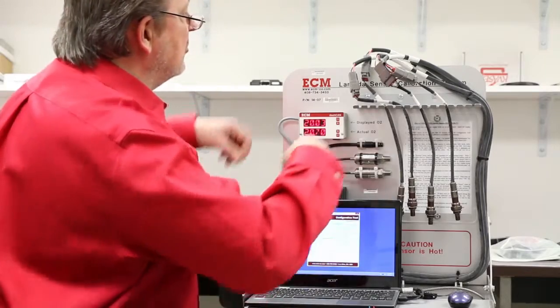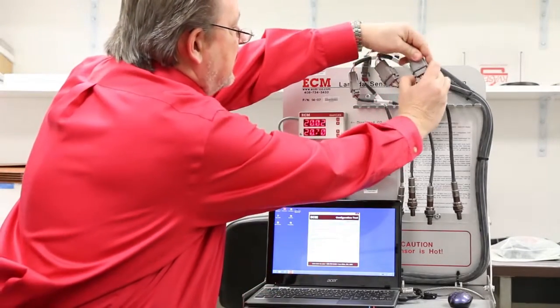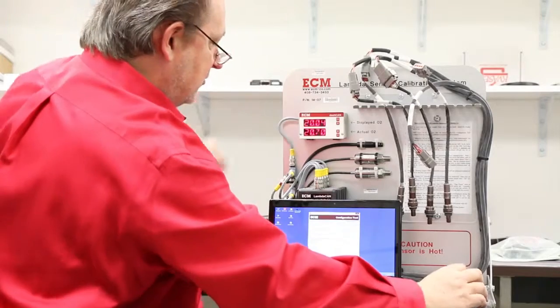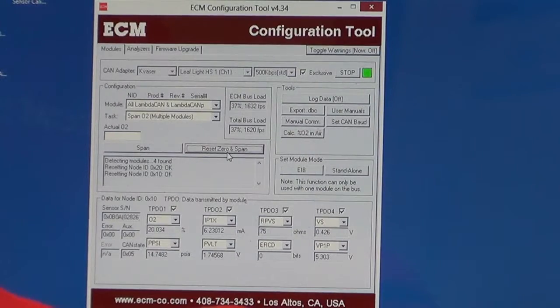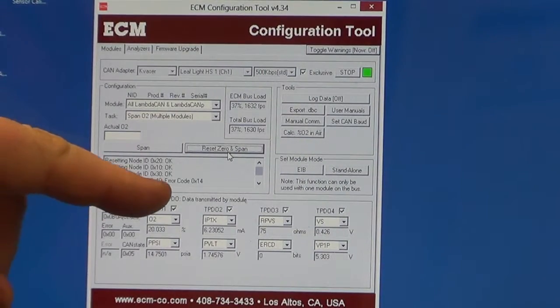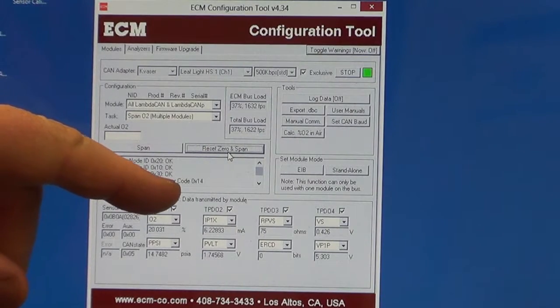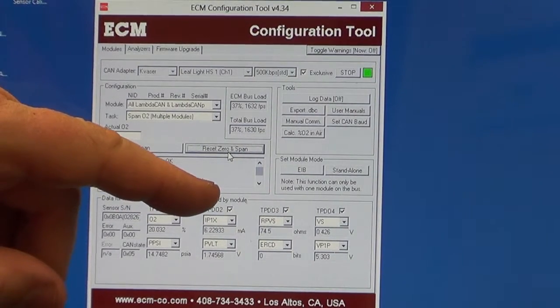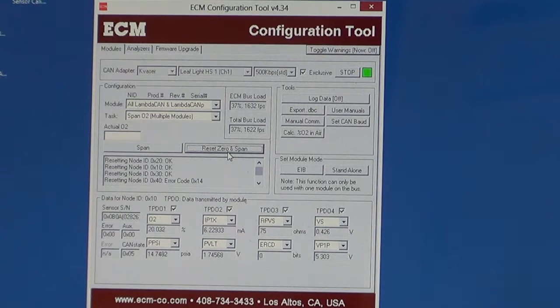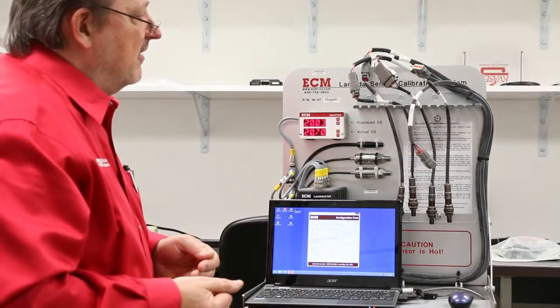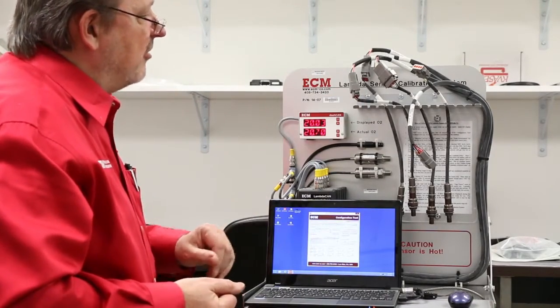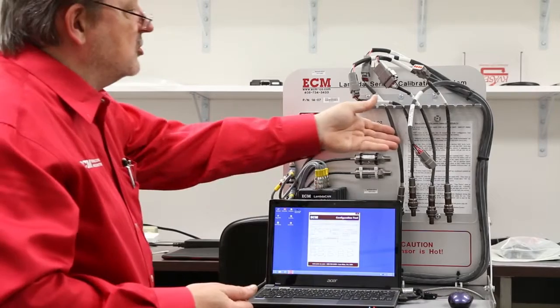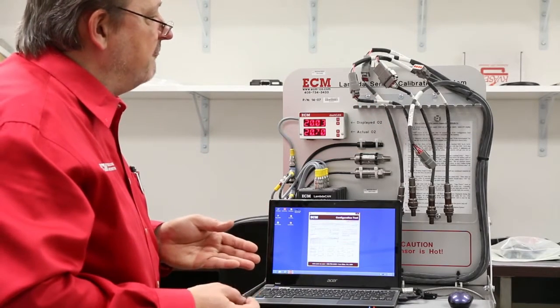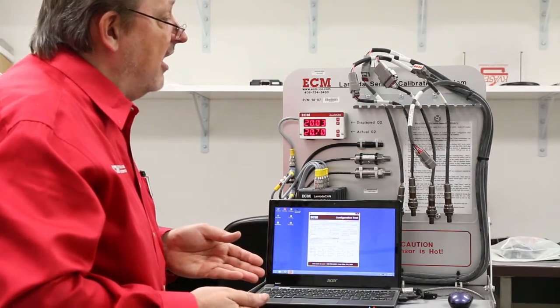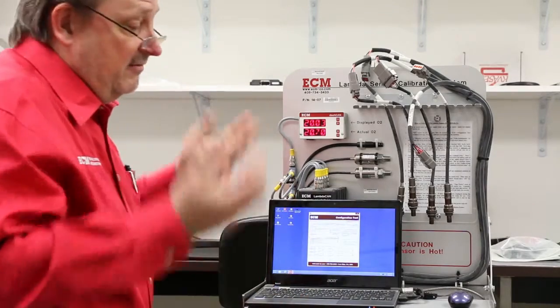Now if you disconnect one of these, I'll disconnect this one here. So if a sensor isn't there and you do that Reset 0 and Span, you'll see that 0x40 has error code 0x14, which means open heater, which means there's something busted inside. So if you don't have a sensor on a cable, it'll give you that error. Don't worry, you can keep on going. You could just be calibrating 3. But if you had a sensor there that gave an error, you're wasting your time calibrating it. You know, throw the thing out.